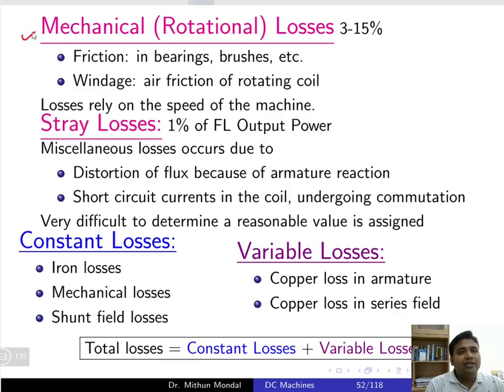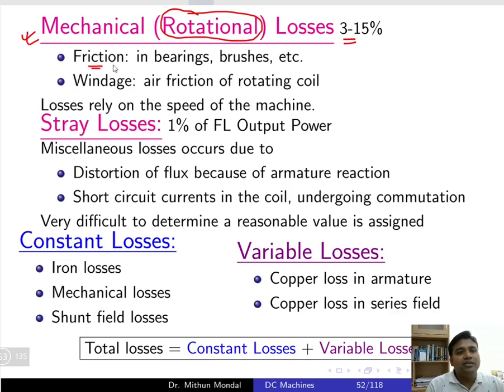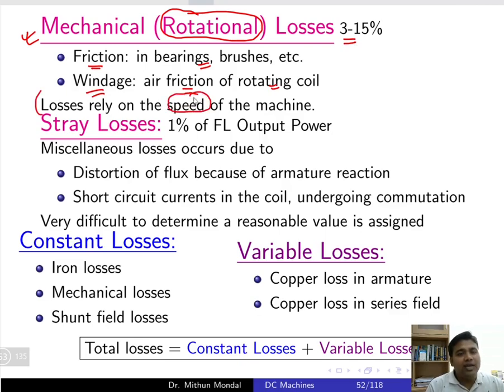Next are mechanical losses, which are basically rotational losses, constituting around 3 to 15 percent. They can be due to friction in the bearings or brushes during rotation, or windage, which is the air friction of the rotating coil. These losses depend on the speed of the machine — the speed at which the machine rotates governs the mechanical losses.